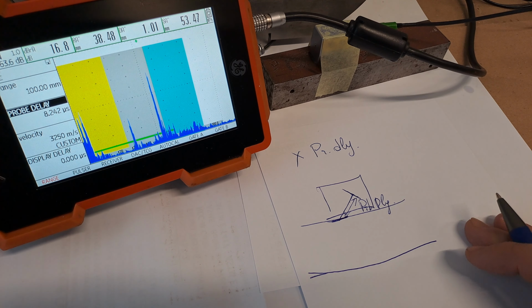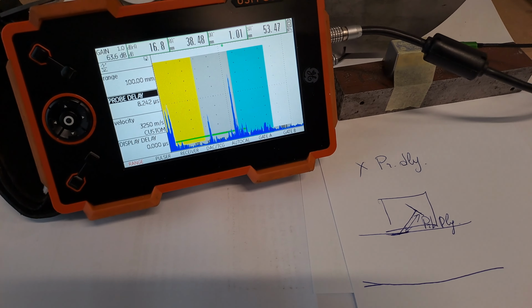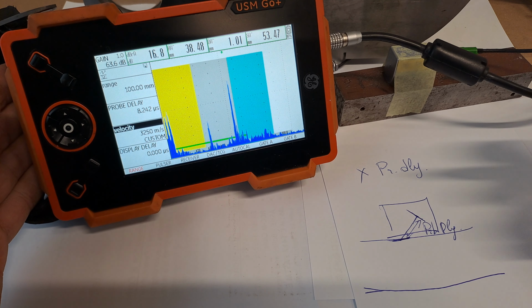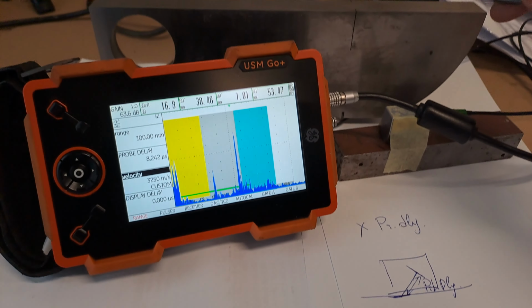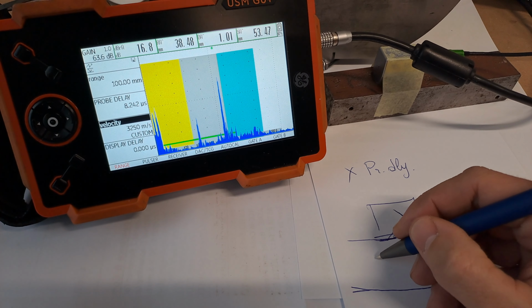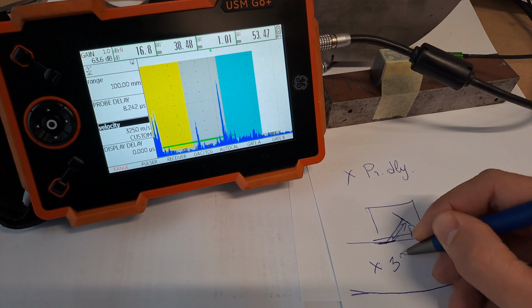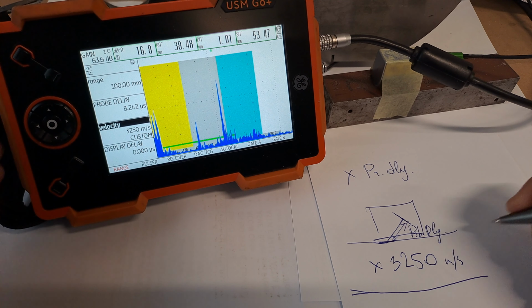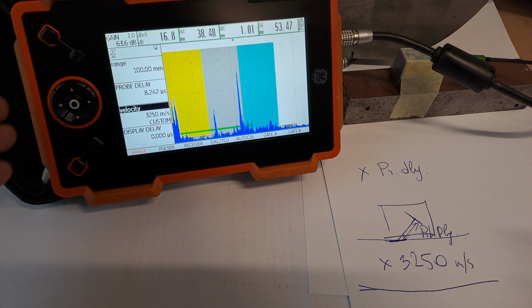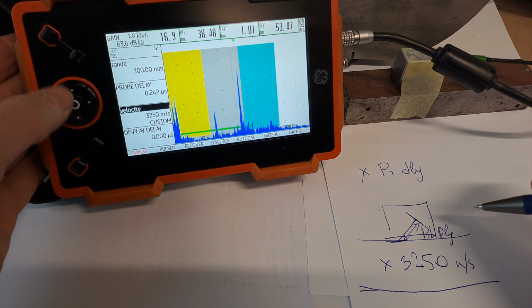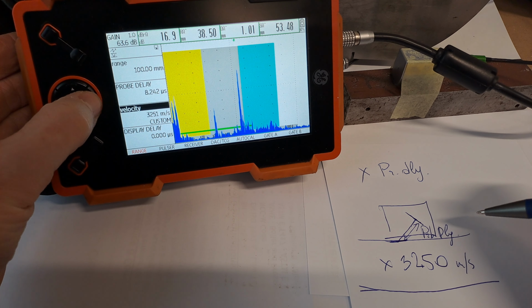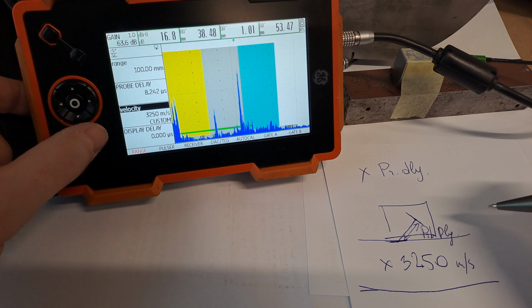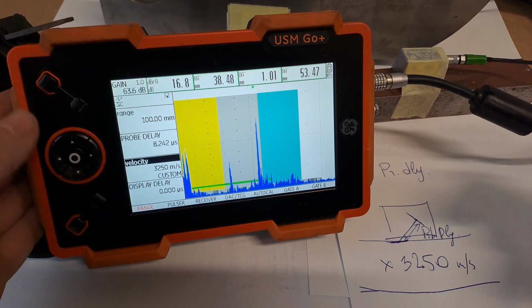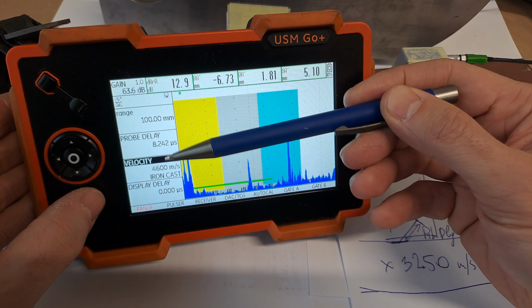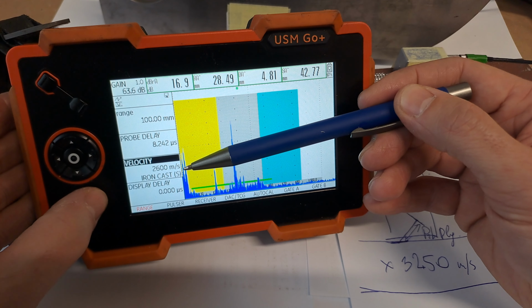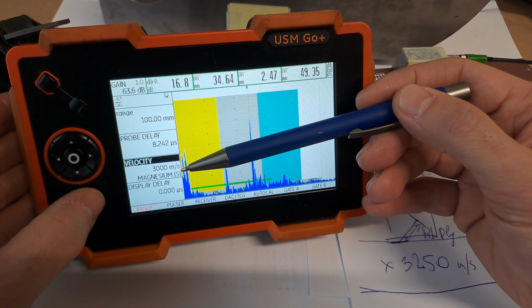The first thing we looked at. Now the second setting is velocity. We know the velocity of this block. The velocity is 3250 in the documentation of the first calibration block. When we know it, we put it here. Now, when we go on it, I can go right or left. If I go with these buttons, what happens is it changes the velocity for the metals: cast iron, lead, magnesium, and things like that.